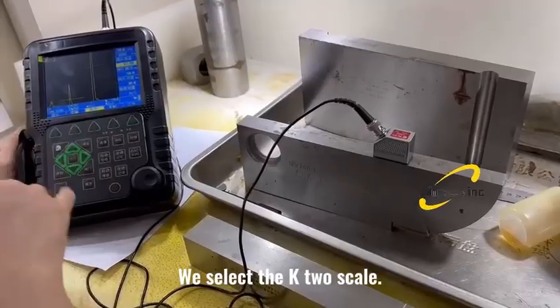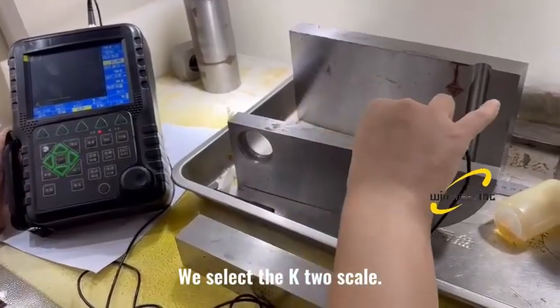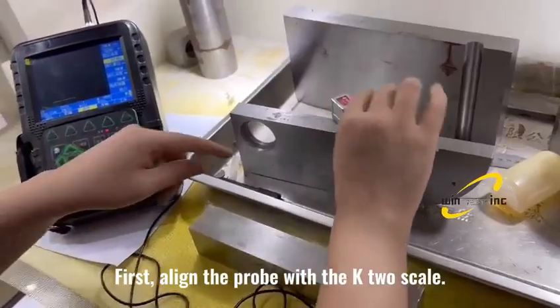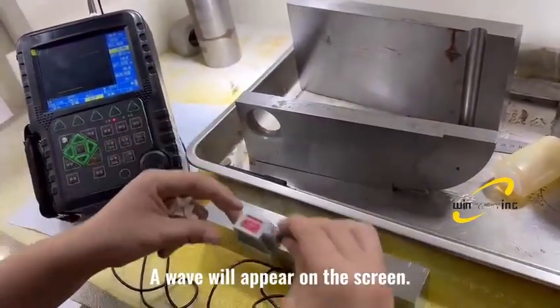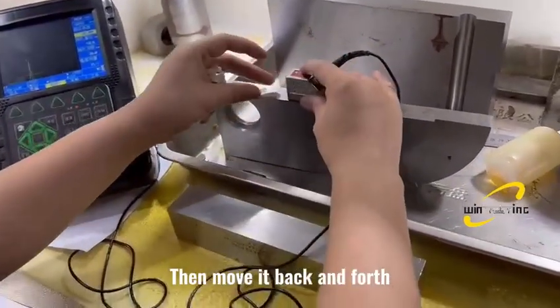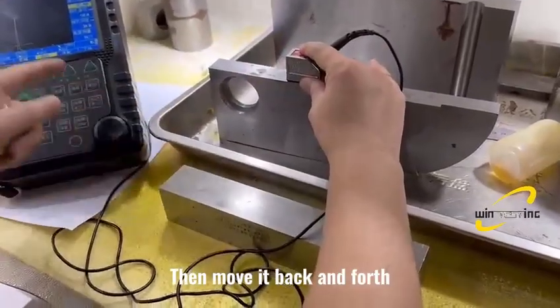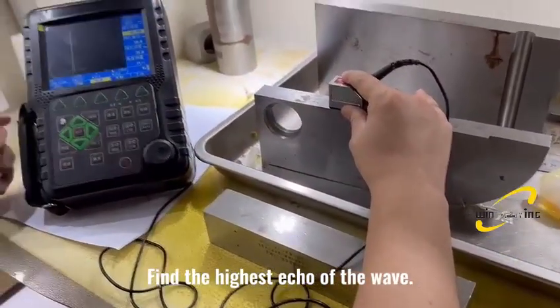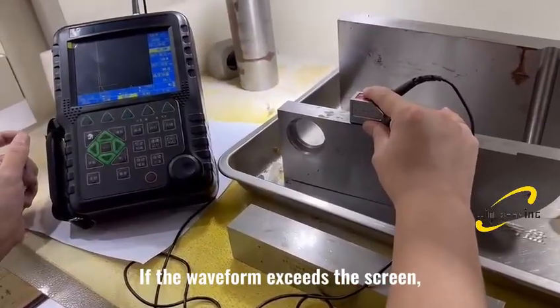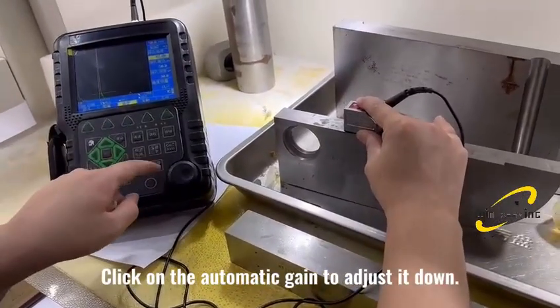We select the K2 scale. First, align the probe with the K2 scale. A wave will appear on the screen. Then move it back and forth. Find the highest echo of the wave. If the waveform exceeds the screen, click on the automatic gain to adjust it down.